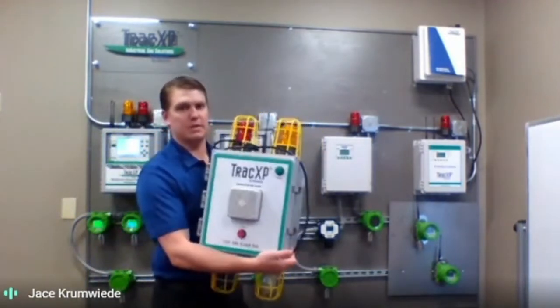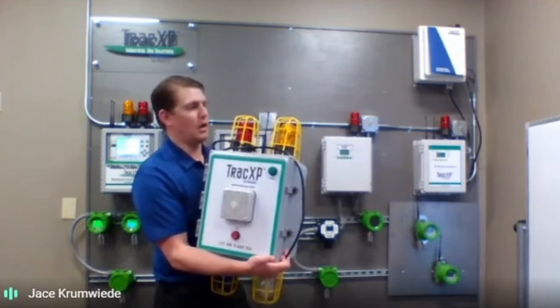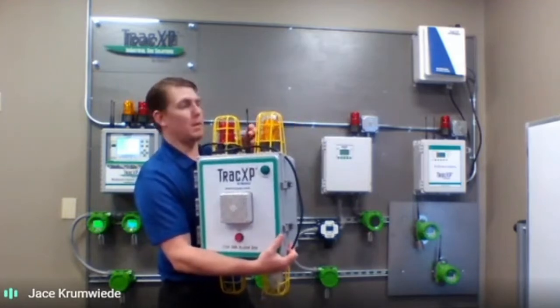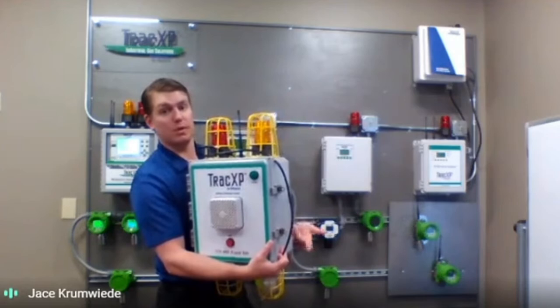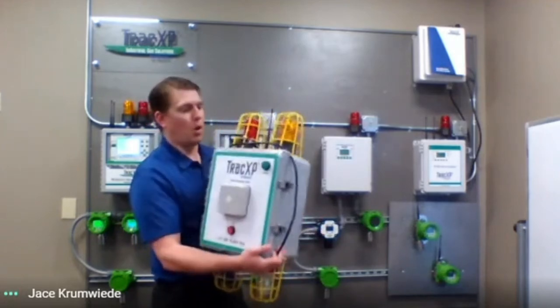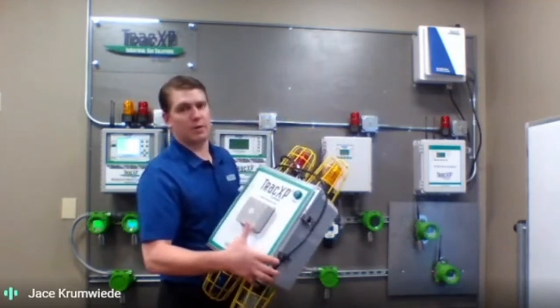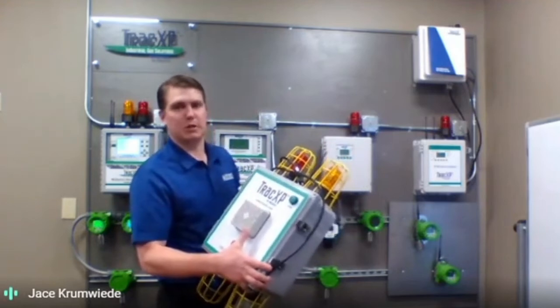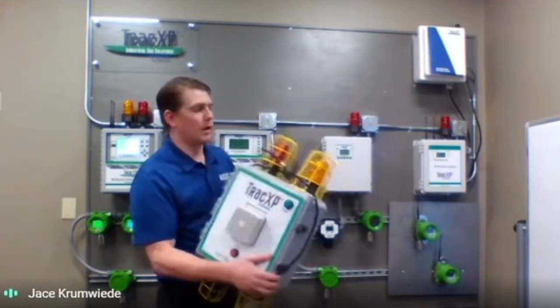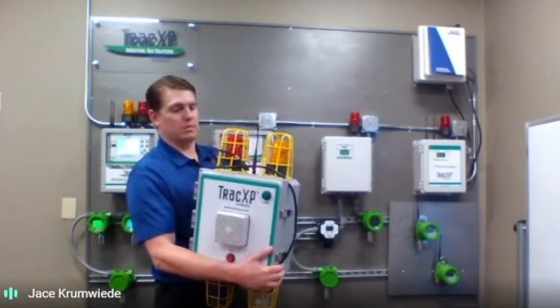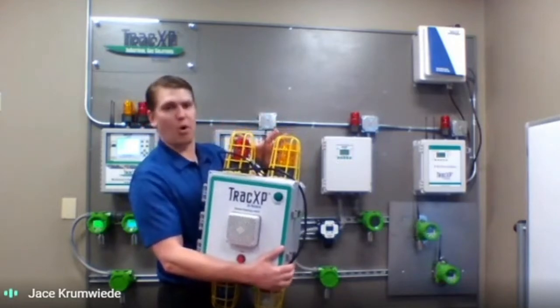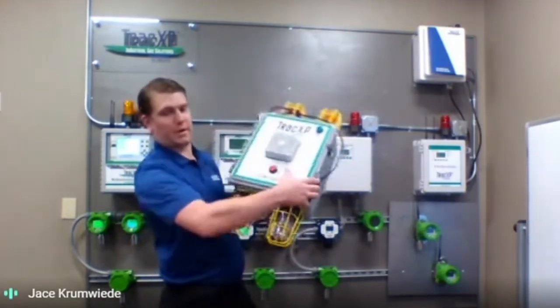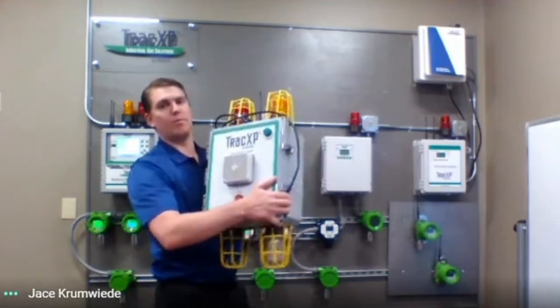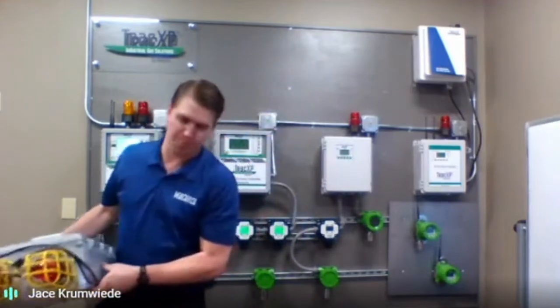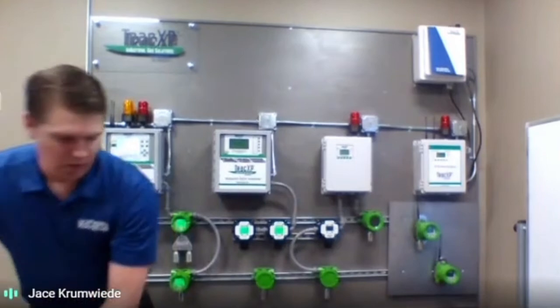This is an ANA, an alarm notification appliance. It's ultimately just an all-in-one notification tool. It can be wireless, communicating wirelessly to those wireless transmitters, or a hardwired installation. So you have your strobe, different options depending on the decibel level you need, and then also various horns and various strobes available. So this one currently has four strobes, so four different alarm conditions it can provide information on.